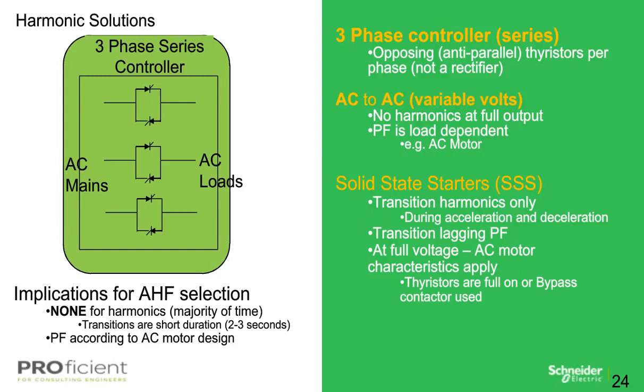is reduced. One very common use for a 3-phase controller is actually a solid state starter, commonly known as a soft starter for AC motors, and this typically helps reduce peak current draws from an AC motor for difficult to start loads. And based on the limited use of the soft starters, they only operate for seconds, so they typically are not considered a harmonic or a DPF problem. But when the AC motor is the predominant load on the AC supply, both harmonics and DPF may be required for reducing.